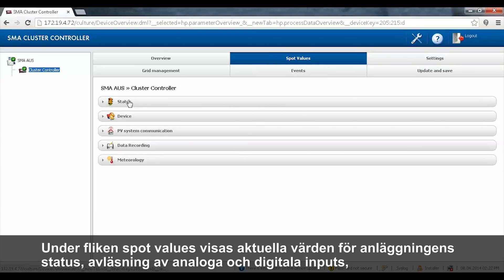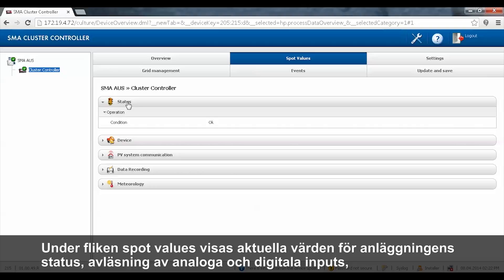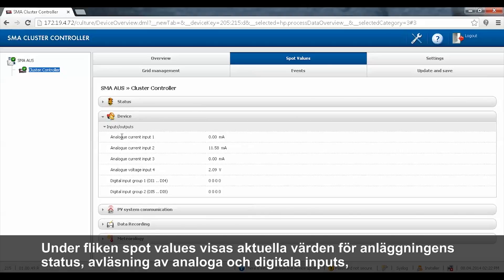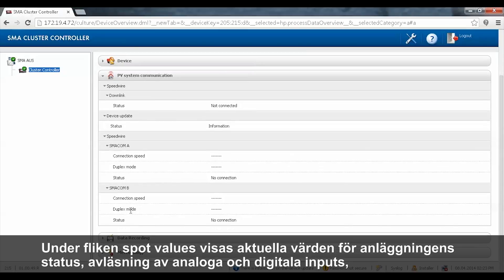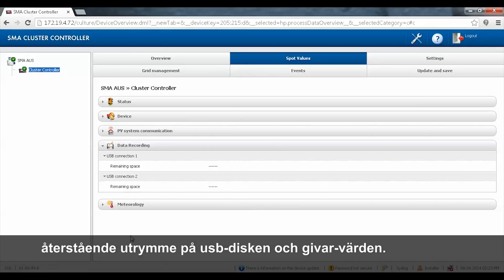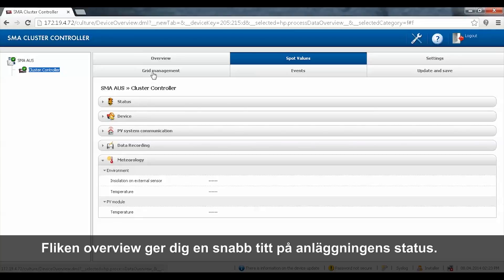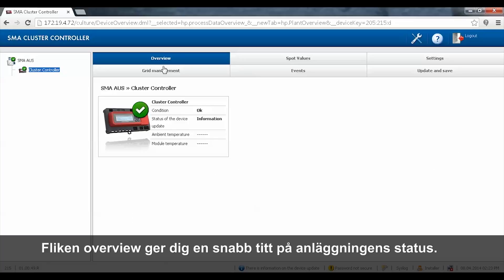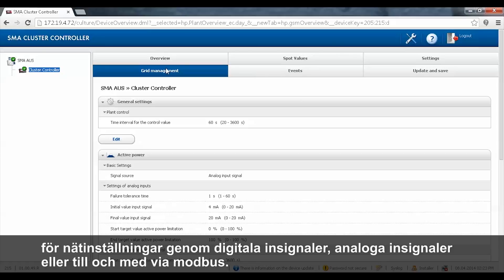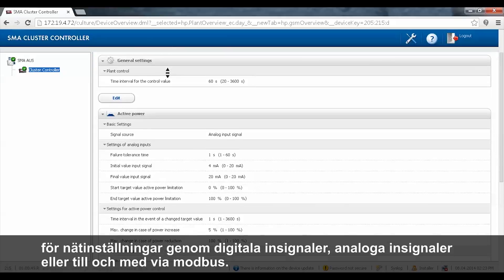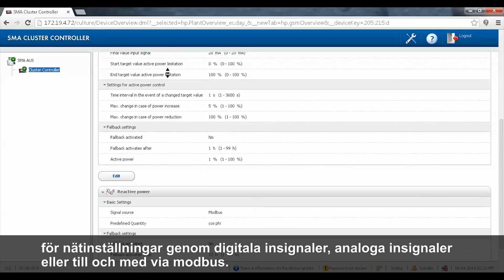The spot value tab gives you spot values of the plant status, the analog and digital input readings, the Speedwire status, remaining space on a USB drive, and the sensor readings. The overview tab gives you a quick look at the status of the plant. The grid management tab gives you access to configure the active and reactive power limitations for grid management via digital input signals, analog input signals, or even Modbus.